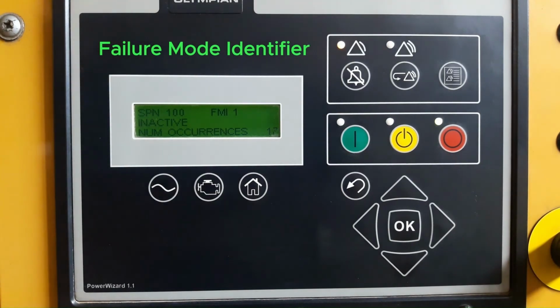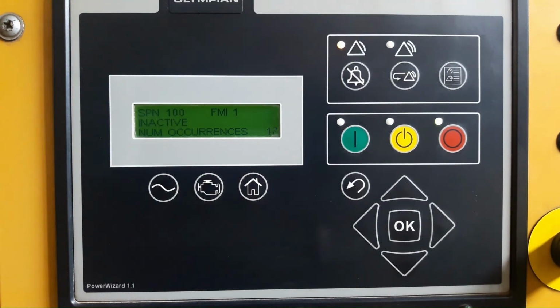SPN is short for suspect parameter number. It identifies which electrical circuit, part or component of your engine isn't working properly. FMI stands for failure mode identifier. This part of the fault code tells you what type of problem your generator has.